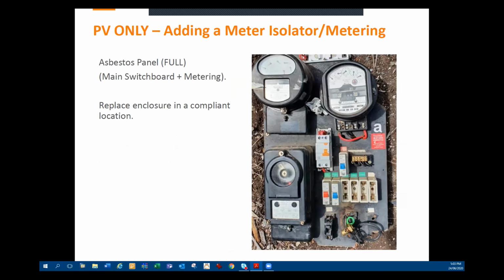So for PV, if you're adding a meter isolator or metering, where there's an asbestos panel, so it's full, basically the main switchboard plus metering, something like this needs to replace the enclosure in a compliant location. We've had some issues where only the meter provider's been involved and an electrician goes into the site and pulls the service fuse, which is in breach of the Electricity Act, does all their work and tries to get it as an upgrade at the same time as replacing the meter panel.